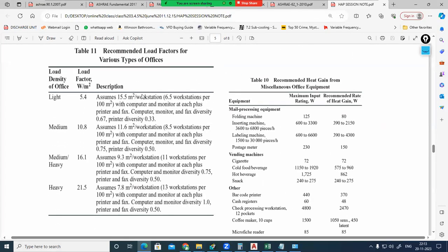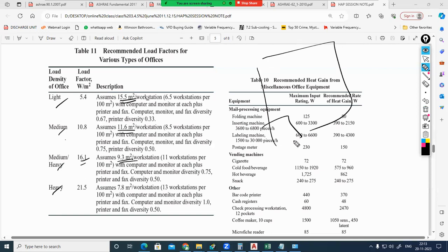This was the table, recommended load factor. Same with this data we can take from the previous version of ASHRAE. There are just four options: light, medium, medium heavy, heavy. Light case means each 15.5 meter square we are assuming a computer. Medium case, each 11.6 meter square. Medium heavy, each 9.3 meter square of floor area. Less area, more computer. Heavy means each 7.8 meter square, you have to assume one computer accordingly.